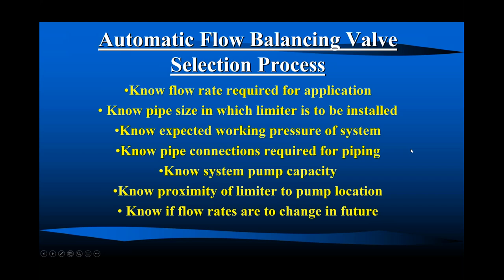Hey, do we have to change this in the future? We may go with one type of automatic flow balancing valve that does not have access to the cartridge. But if it is going to change, maybe we put access in there. I want to go from 5 to 8 GPM later on. And again, most reps do this. Really just the terminal unit schedule, which is already what you have to do, send that out, and you can get a corresponding automatic flow balancing valve schedule.